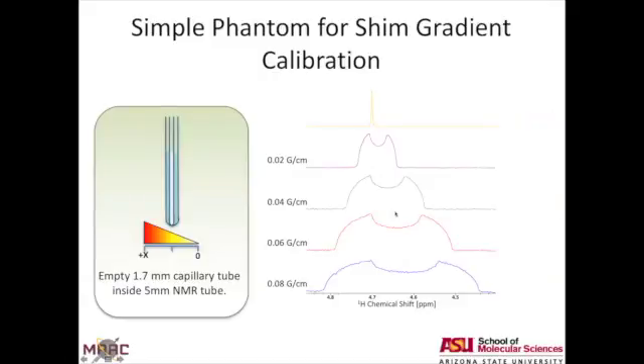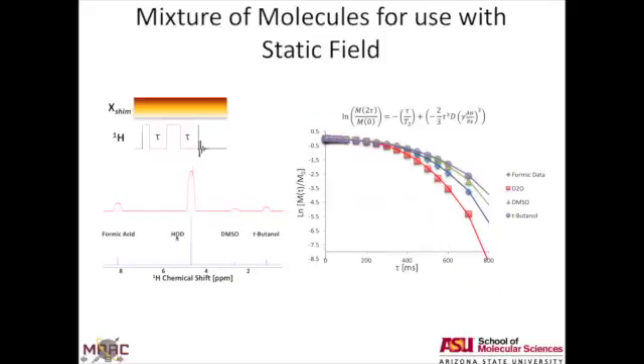And so, again, you can have a simple phantom to calibrate this, in this case, an empty capillary tube in the middle. But one thing I do want to point out now is that when you put this into practice, it's best to use an X or a Y shim for a couple reasons, as opposed to a Z shim. The reason is that your sample is wholly contained within the RF coil. So, in the Z shim, where it's not the case, you have problems where you have a B1 field roll-off, so your image is not clean and precise. But also, you have the fact that your sample may not be centered within the coil, and then your probe may not be perfectly centered within your shim set. So, you get frequency shifts associated with a Z1 shim that may complicate things. You avoid that by going to an X or Y shim. And this even shows, like, I was worried when we first thought up this, you're probably going to have to make the gradient big enough that you're going to lose so much resolution, which you also lose signal to noise like crazy, you're probably only going to be able to do one component. But as we can see, you get enough of a T-cube drop off that you only have to broaden it a ppm or less.